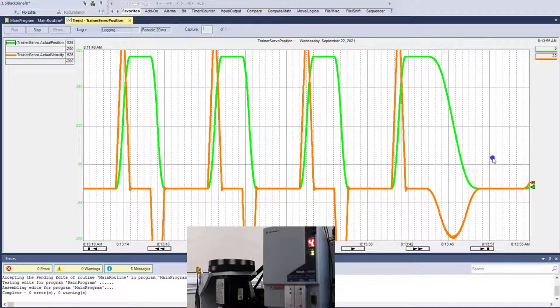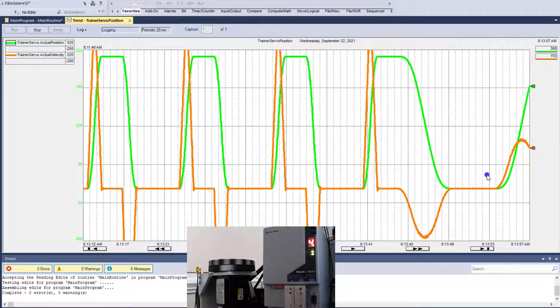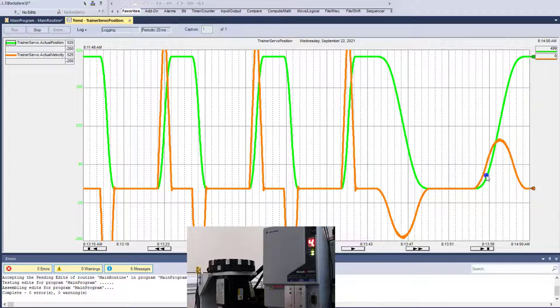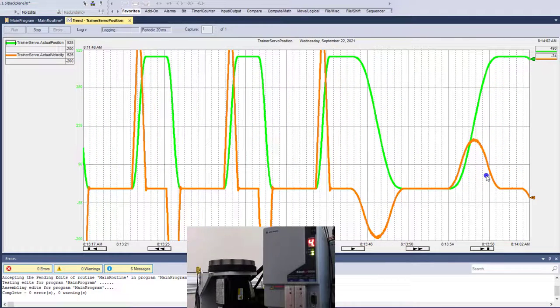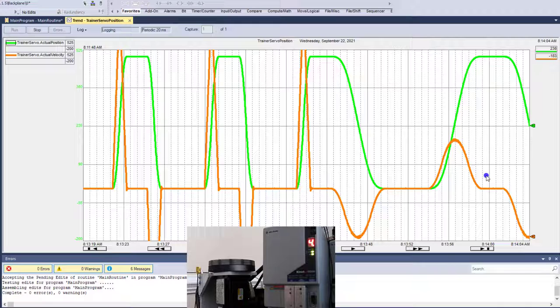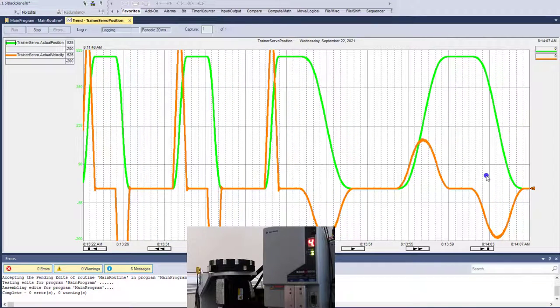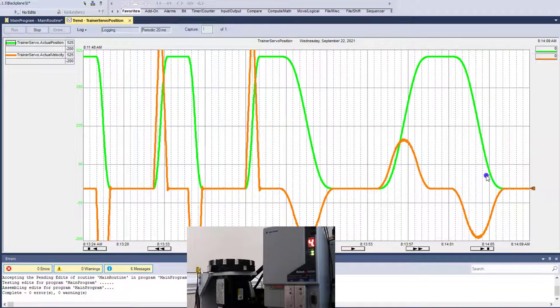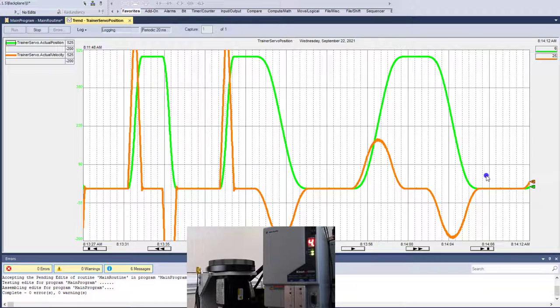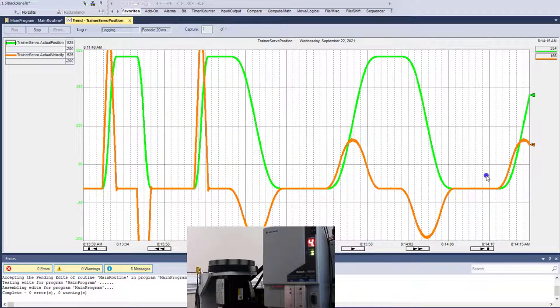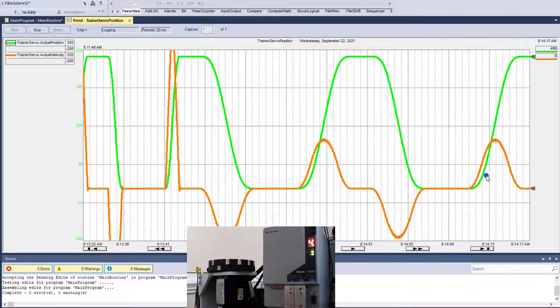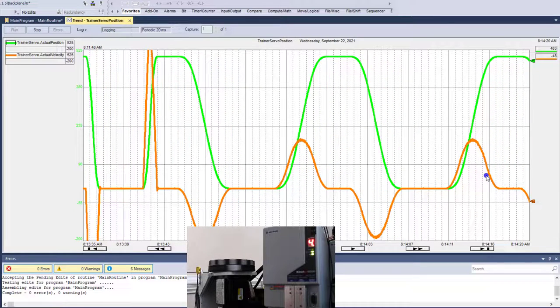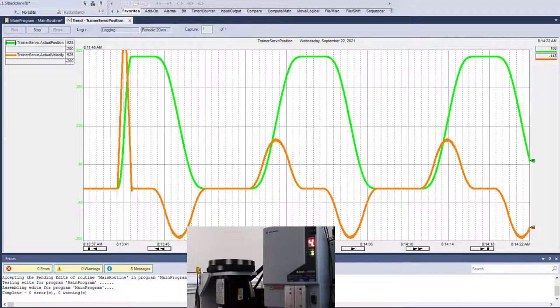And that just goes, and that, again, tuning an S curve is a lot easier than you think. But keep in mind, the tuning of the S curve depends upon your machinery, depends upon what gearboxes or pulleys or how many different attributes or mechanical attributes you have attached to your servomotor. So keep in mind, all that will be equated based upon actual movement. Generally speaking, you do that in your conversion constants.